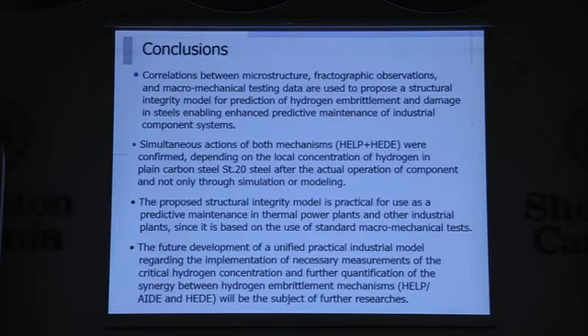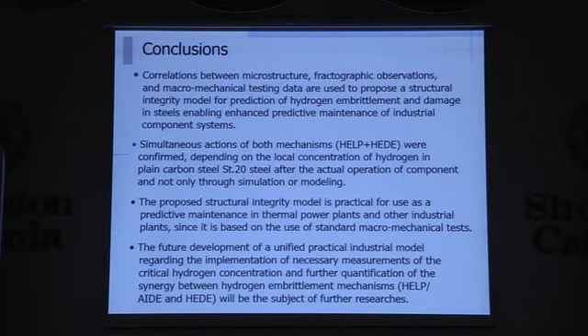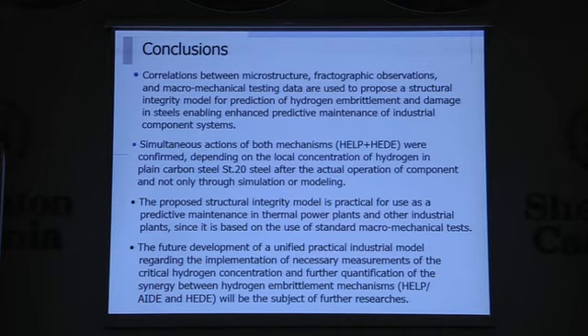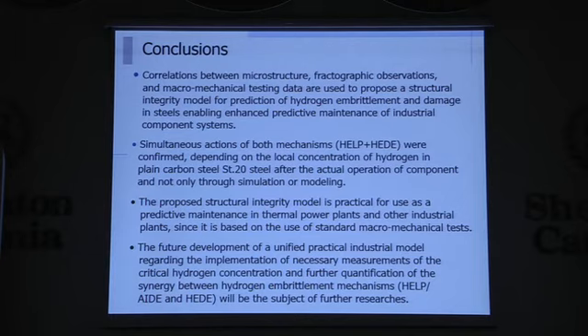Here is the conclusion: correlations between microstructure, fractographic observations, and macro-mechanical testing data are used to propose a structural integrity model for prediction of hydrogen embrittlement and damage in steels, enabling advanced preventive maintenance of industrial systems. Simultaneous action of both HELP and HEDE mechanisms was confirmed depending on the hydrogen concentration in plain carbon steel after actual operation of components — not only through simulated or modeled specimens, but real components. The proposed structural integrity model is practical for preventive maintenance of thermal power plants and other industrial plants, since it is based on standard macro-mechanical tests. Future development of a unified practical industrial model will address critical hydrogen concentration measurement and further quantification of the synergy between these two mechanisms.